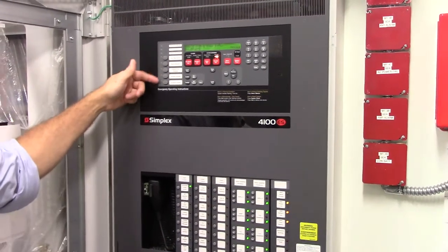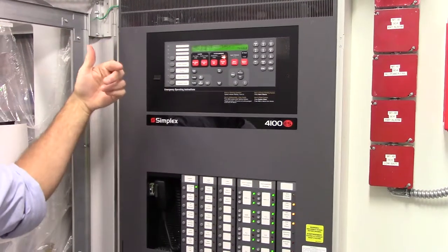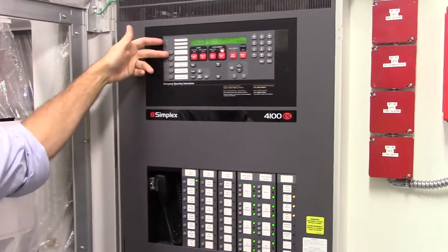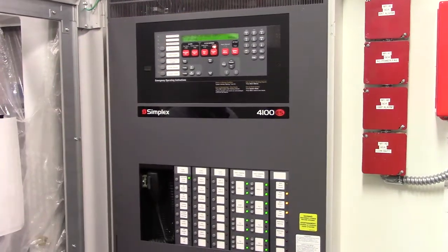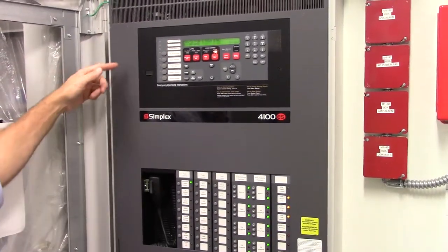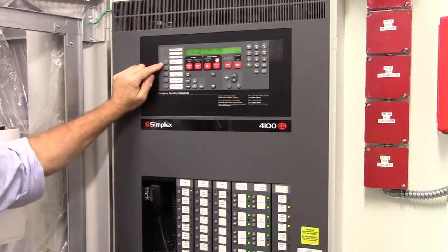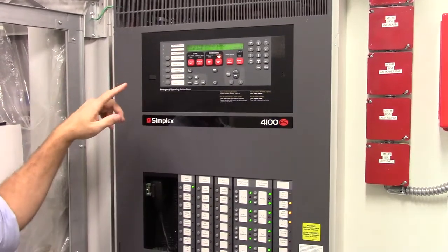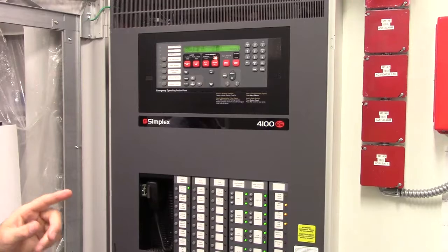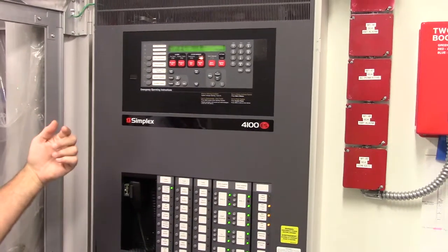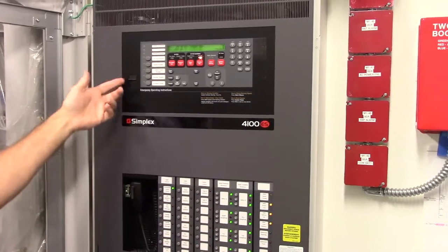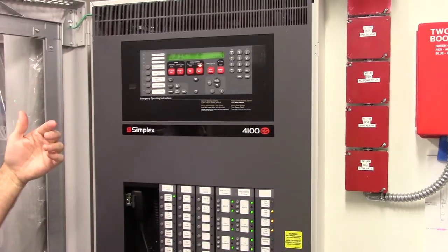Same bypasses here as we tried to keep it consistent for the rest of the campus. So you got your city disconnect, which will actually disconnect this building from the radio master box. Just so you guys know, with the radio master boxes, when you hit the city disconnect, it will still send them a signal. Zone 6 on the radio box is set up for city bypass so that they know somebody is here working on it with bypass active. Signal bypass obviously kills all the horns and strobes in the building.